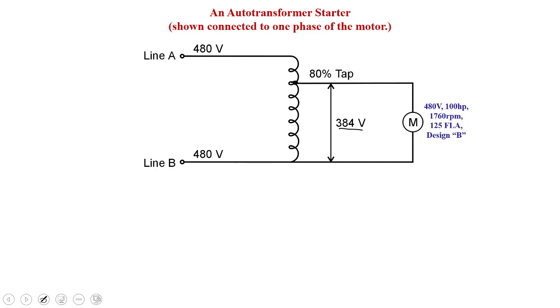We've got a 480 volt motor, 100 horsepower. Its full load RPM is 1,760 RPM. It's 125 amp full load amps, and it's a design B rotor. If I wanted to look at the starting current, I know that a design B rotor is about 500% inrush. The FLA of this motor is normally around 125 amps. So 500% times 125 amps is 625 amps. That's quite a significant amount of current.